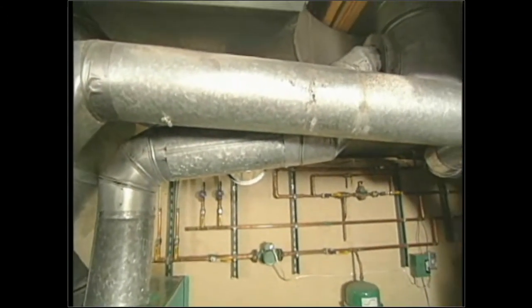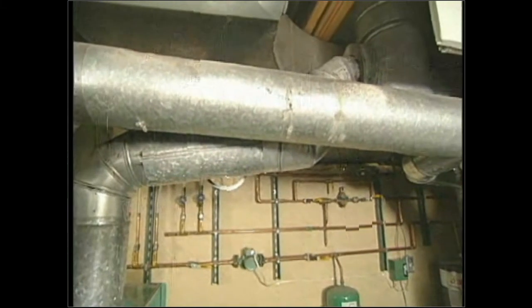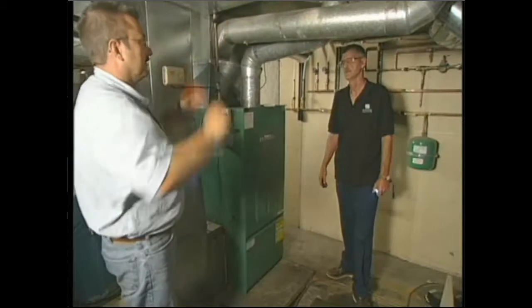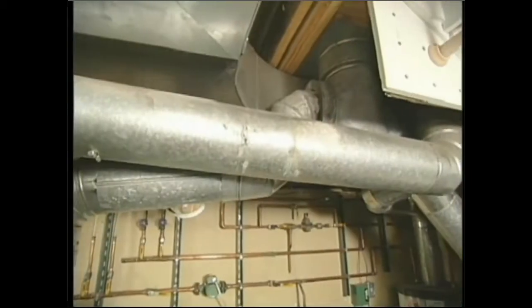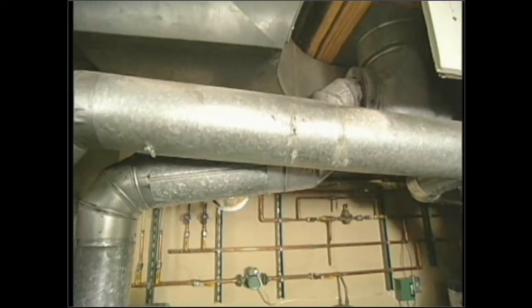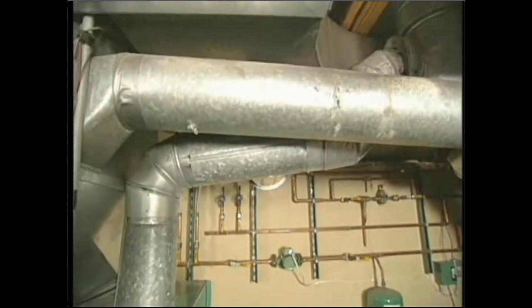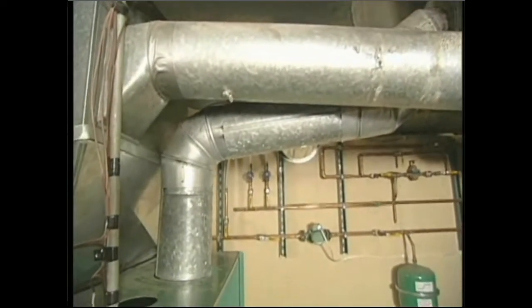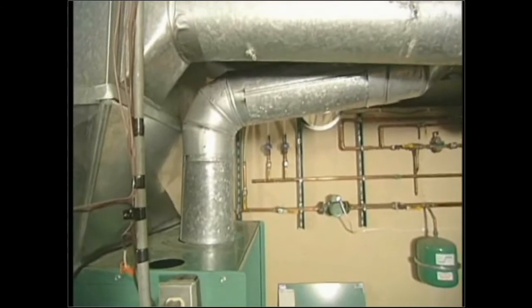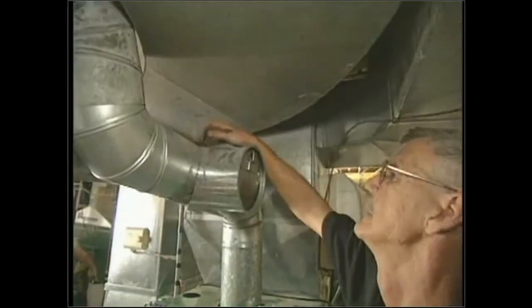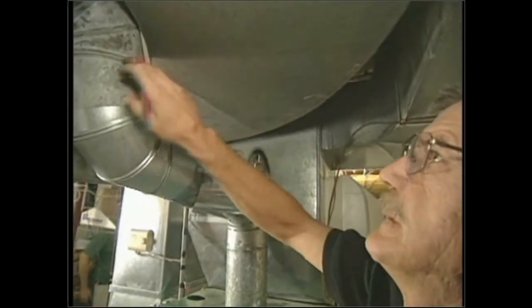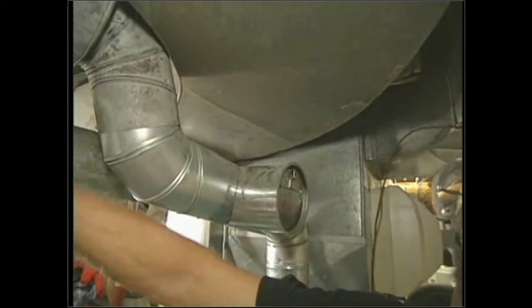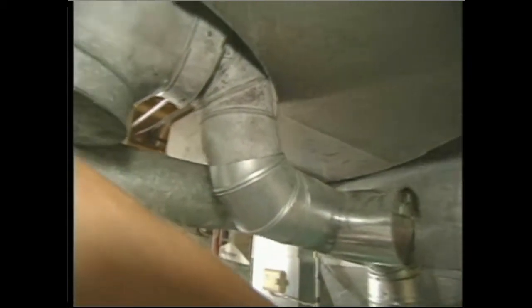So really, you're checking that to make sure there's a clear airflow all the way up there, no obstructions in there, so that it's clear venting to the exterior. Yes, we want to have this unobstructed because that's how all the combustion gases get out of this house. There's no draft assist. It uses its own temperature difference to make it rise out of the house. Another thing we do is a visual inspection of the chimney itself. This is a single wall interior chimney, so it doesn't have a clean out door. It only has a clean out cap. Well, I'm not going to pull that down right now because I don't have the correct equipment to catch everything in case something comes out of there.